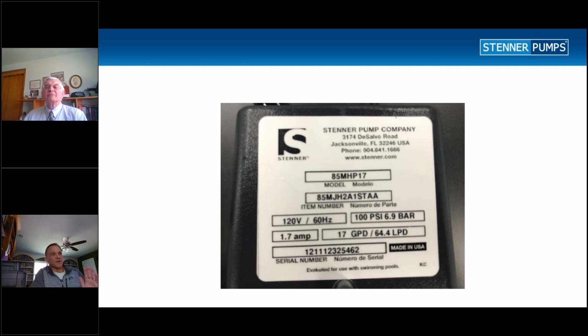So after hearing this, more than likely when I hear that part number, I would know that this pump had a number 2 tube in it. One thing that's so nice about a Stenner pump is that if your flow rates are too high or too low, if you need to increase or decrease the flow rates, you can always adjust that flow by changing the tubes. And then on the bottom here, you'll see a serial number.